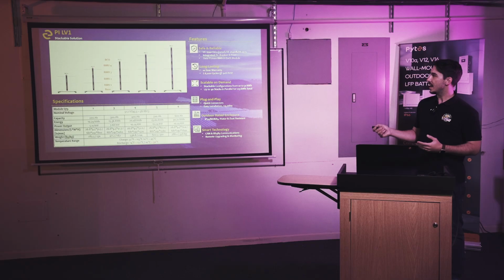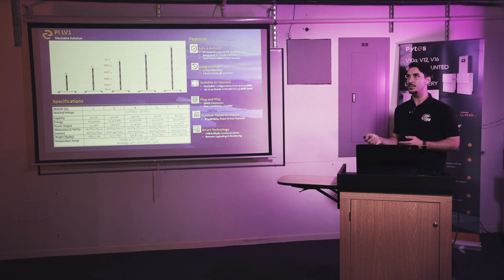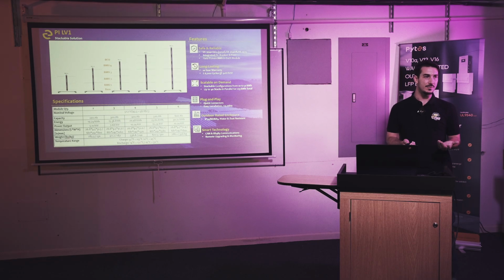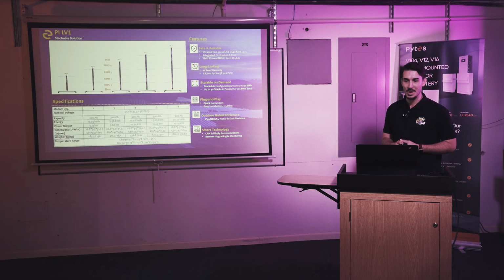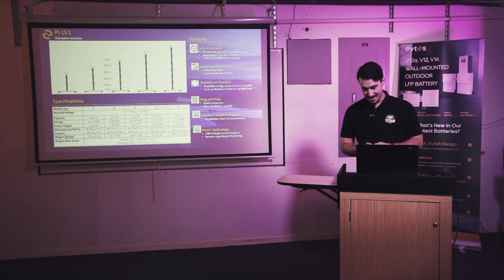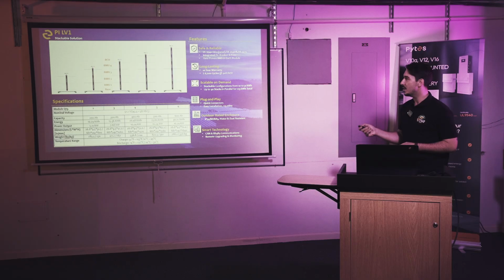Minimum you can do 2 in a stack, maximum is 6, and now I believe we can do up to 8 groups of 6 in total. So it's not quite as scalable as the V5—and I should mention, with V5 you can do up to 96 of those batteries in a common system, just shy of 500 kilowatt hours. That'll cover pretty much any residential project I've worked on, and even small commercial stuff. So a couple other things to point out about Pytes.